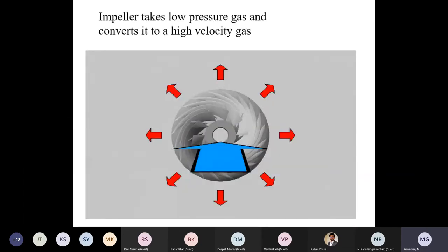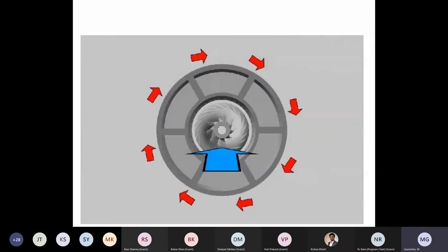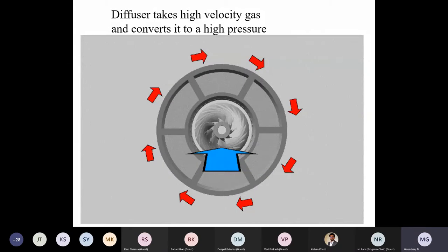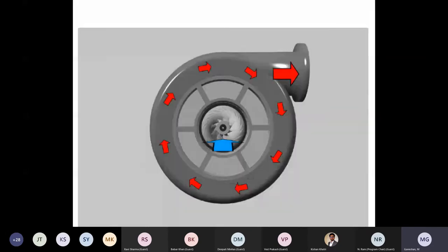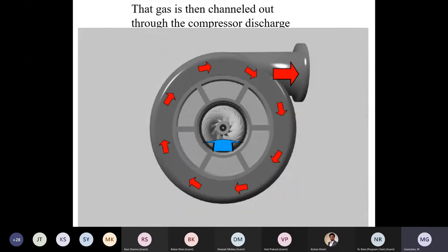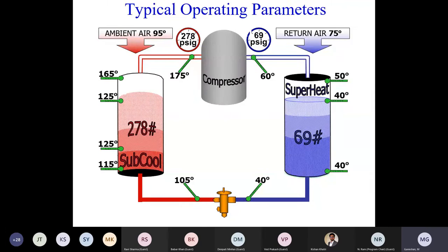As for the function, the low pressure gas comes into the eye of the impeller. Because of the high rotating speed, the velocity increases. The high velocity gas then passes through the diffuser, where the high velocity is converted into high pressure. By the time it comes out of the discharge volute, the pressure has increased, and then it goes into the condenser, giving off the heat. This is how a centrifugal chiller works, like typical pumps. These are the operating pressures in any normal, simple, saturated system.